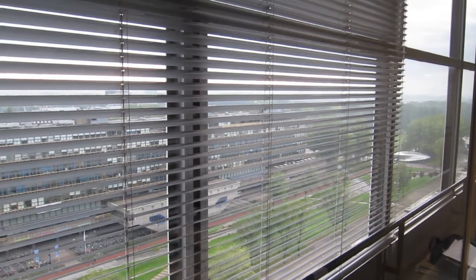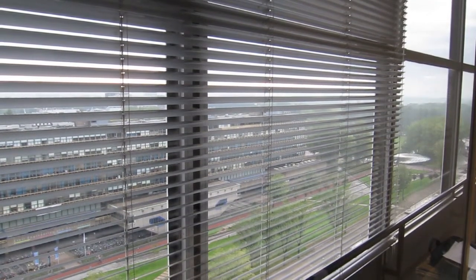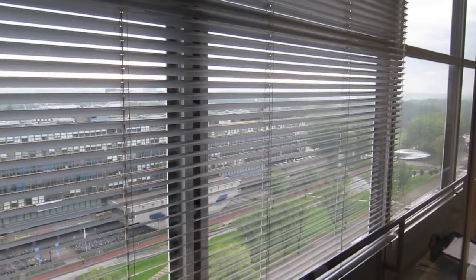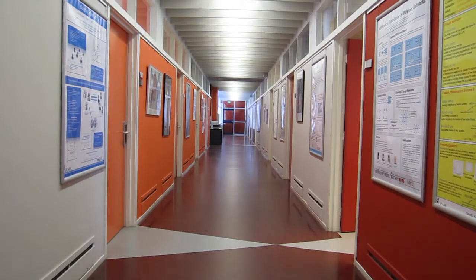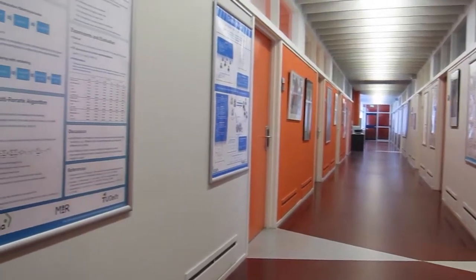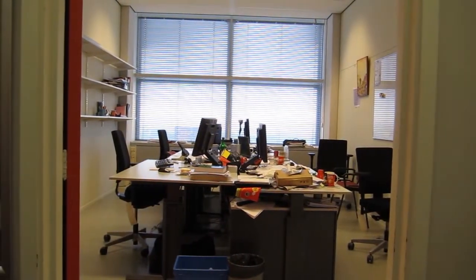The sun shading that is integrated into this facade keeps the warmth from entering the building, but gives little room for adjustment of these conditions. Unfortunately, the heat trapped in the facade in the summer is poorly ventilated. The warmth then infiltrates the building, creating a bigger need for cooling and an uncomfortably warm window. This doesn't help in establishing a comfortable climate, nor in reducing the energy expenditure to maintain it.